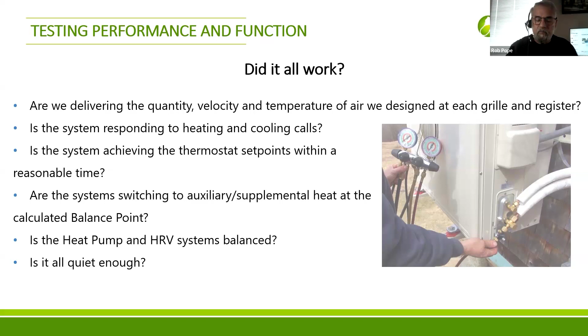But what I've just been talking about is really performance, right? And performance is like what you see on the stage. That's the performance. Is it delivering the comfort that we were expecting to deliver, that we wanted to deliver? But behind the curtain, we have function, and that's all the technical stuff that makes that all work in front of the curtain, right? And it's more technical, and it's something that you really need the proper tools and gauges and so on to test. And of course, you need to have the know-how to do it. So utilizing appropriate tools and devices to measure airflow. So you're going around with an anemometer, for example, and looking at what CFM, velocity and temperature the air is coming out of each of those registers.